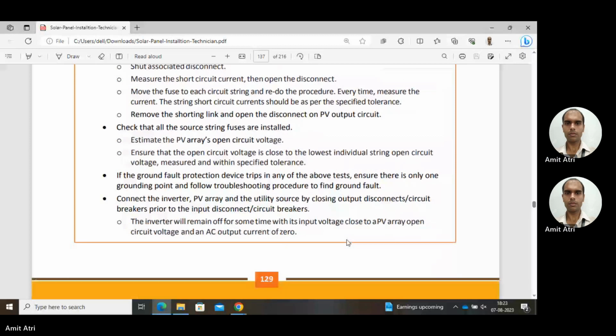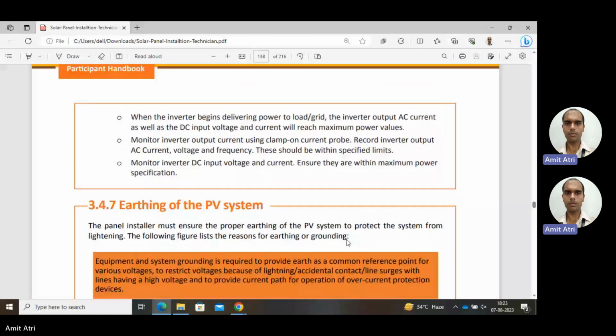The inverter will remain off for some time with its input voltage close to the PV array open circuit voltage. For some time the inverter is off with the applied voltage of the output from the PV array. We have applied it to the inverter and still, we have not switched it on instantly. So when the inverter begins delivering power to the load or the grid, means you have switched it on. After that is connected, then you switch it on.